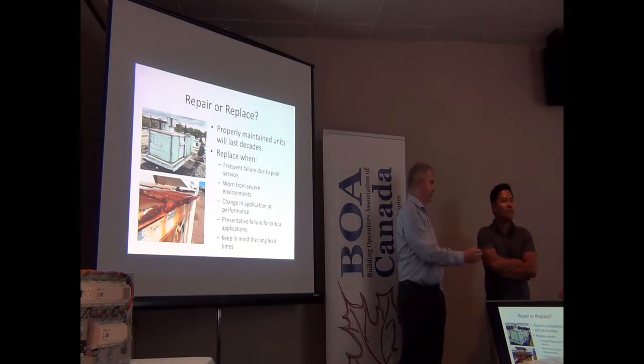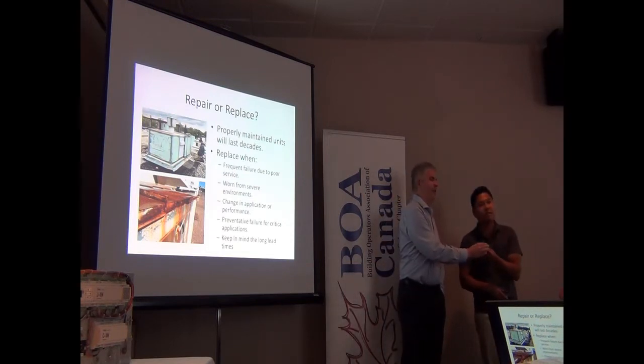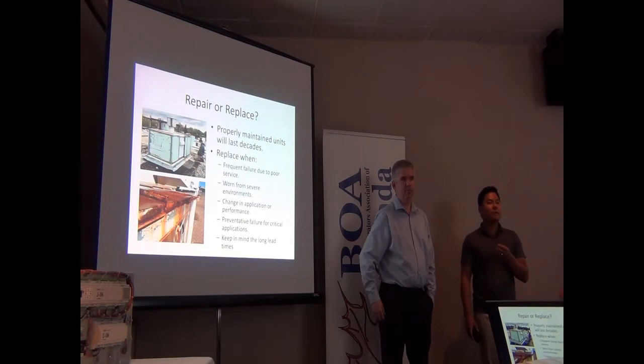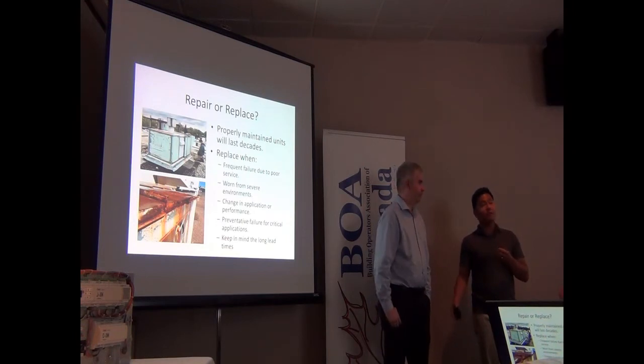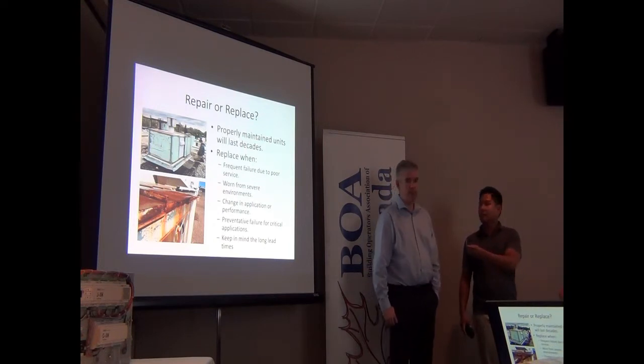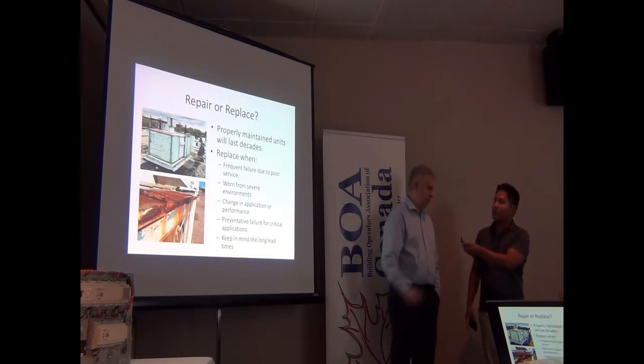But of course, if you're going to jump to a HEPA filter, that's a whole other story. So we'll take a look at what filter you want to upgrade to, and look at the fan curve. If it's adding a lot of static, you're going to lose airflow, and you need to get it rebalanced. Okay, good, thank you. We'll talk about replacements.